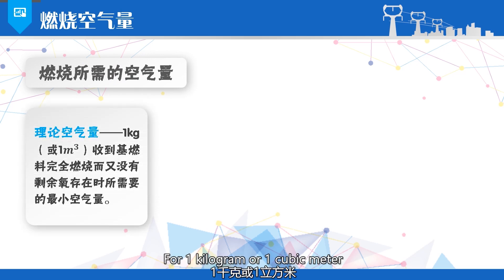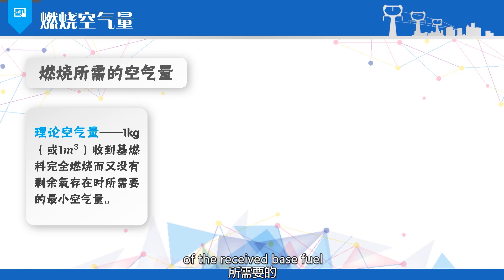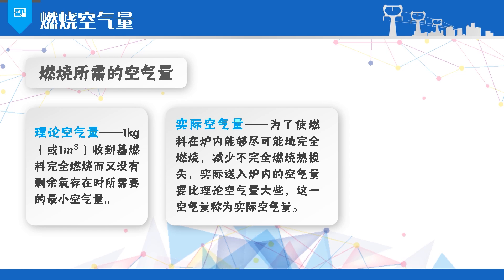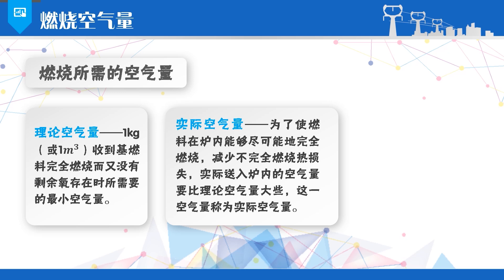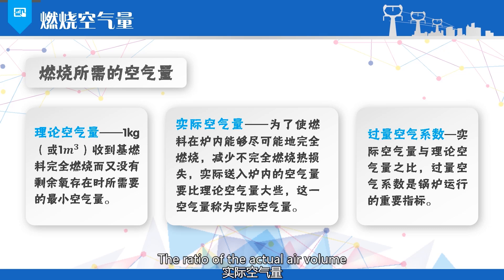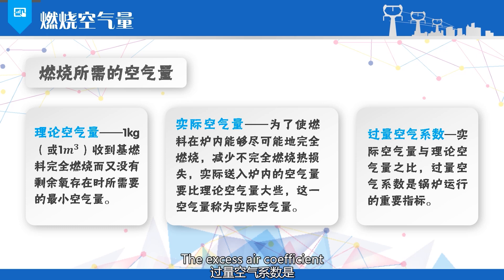The minimum amount of air required for complete combustion of one kilogram or one cubic meter of received-base fuel with no residual oxygen present is called the theoretical air volume. To ensure that the fuel in the furnace can be as completely burned as possible, reducing the heat loss from incomplete combustion, the actual amount of air fed into the furnace should be slightly larger than the theoretical air volume. This air volume is referred to as the actual air volume. The ratio of the actual air volume to the theoretical air volume is called the excess air coefficient.